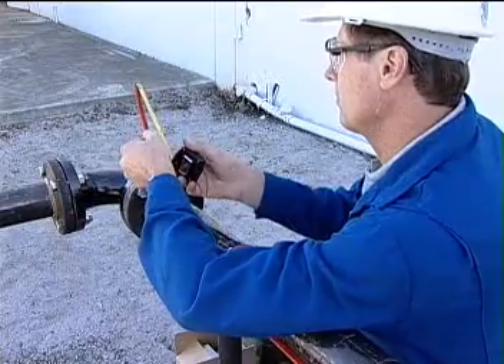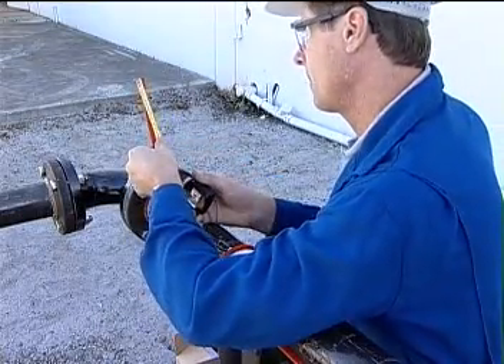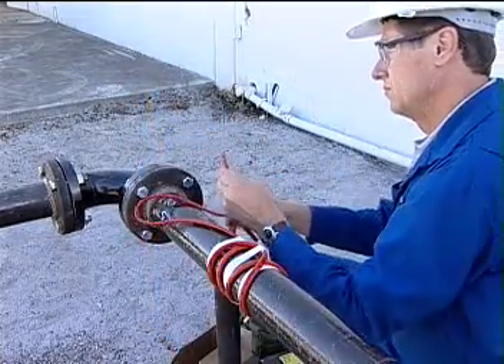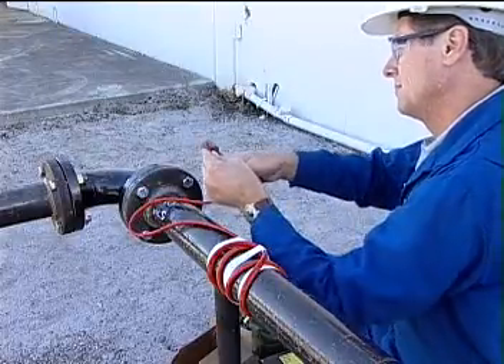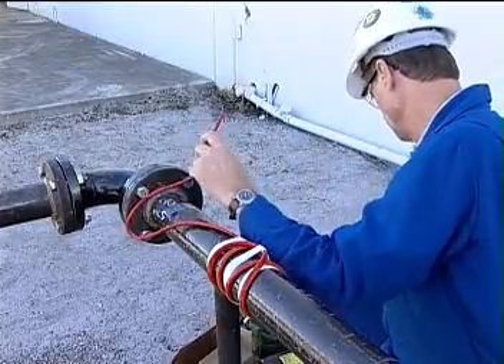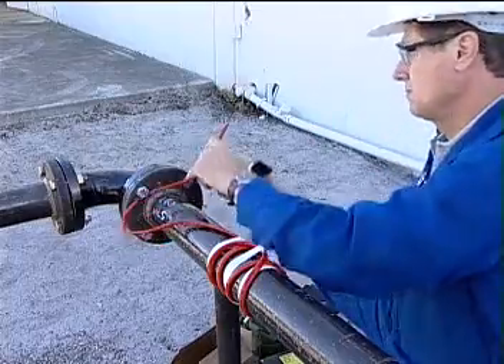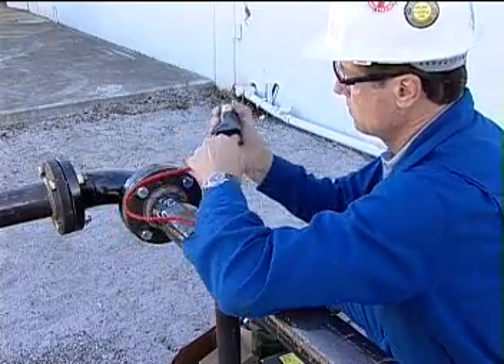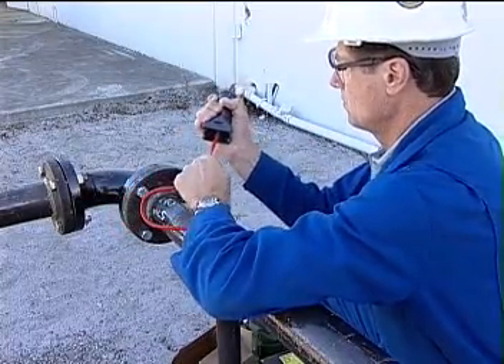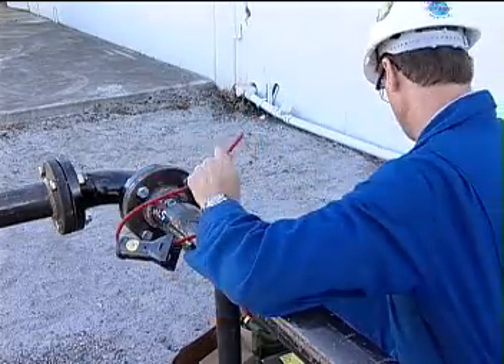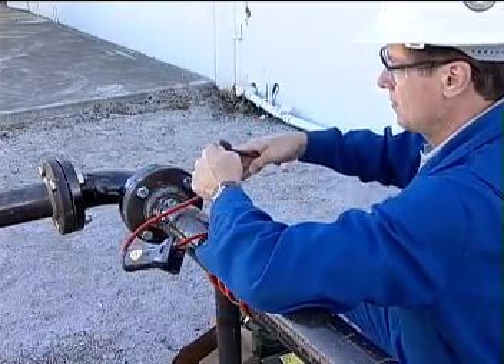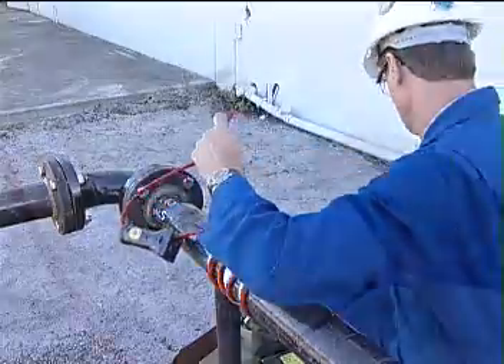When preparing to make the connection, allow 18 inches of heating cable to make the connection. Cut off the heating cable end at about 45 degrees for easy insertion. With the label on the stand facing the desired position of the box opening, push 12 to 18 inches of heating cable through the stand. Square off the cable end with a 90-degree cut. Do not attach it to the stand yet.